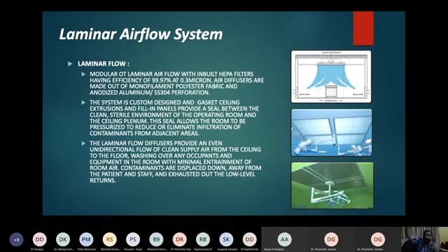The air comes through just the top of your operation table, and the four sides of your modular operation theater have return air duct outlets, with grills made of steel or duly powder coated, on all four sides. So the air will come through the top and be sucked out through the four sides of your operation theater. The laminar airflow system comes with a HEPA filter inbuilt. Normally it comes in a standard size, made of aluminum, or it can be made of stainless steel 304 grade as well.